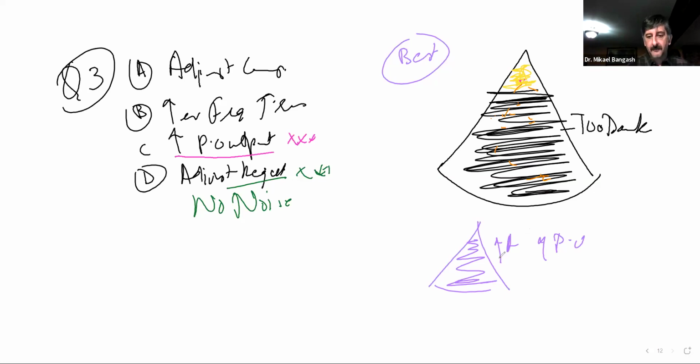Now, of course, if both of these were written as we had above, then you can say increase the amplification would be the best because it brightens up our whole image. Please keep in mind that it's going to brighten up the whole image. And in this case, also, do not increase the patient's exposure, because what we do in amplification is that the signal that returns back from the patient to the system is being increased in intensity.